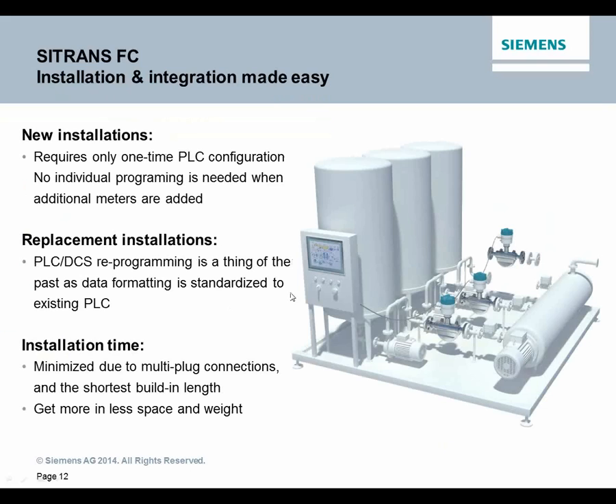All right. So the fundamental design of the new Coriolis meters is to make everything as easy as possible. Now, there are devices that we have that have displays that make the regular installation without a PLC or a DCS very simple. It's all wizard-driven with on-screen menus that walk you through what to do for first-time setups. Like I said, the newest of the new is this digital interface for Modbus, which you plug into your DCS or your PLC, and you turn it on, find the units, and set your limits, and you should be good to go. The greatest benefit there, of course, is that if you pull one of these units out for service or recal or whatever, and you put another unit in, the programming is still there, so you do not have to reprogram.